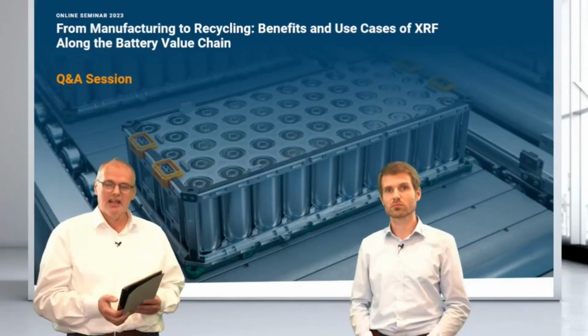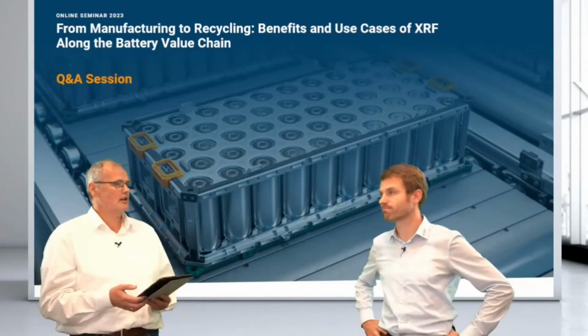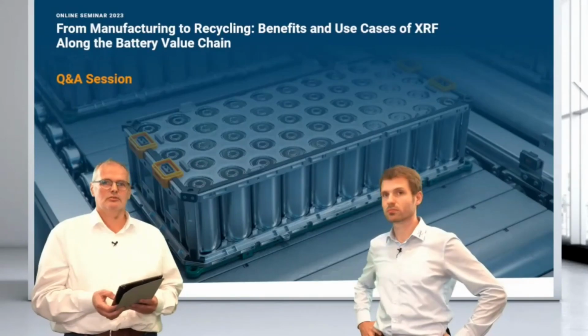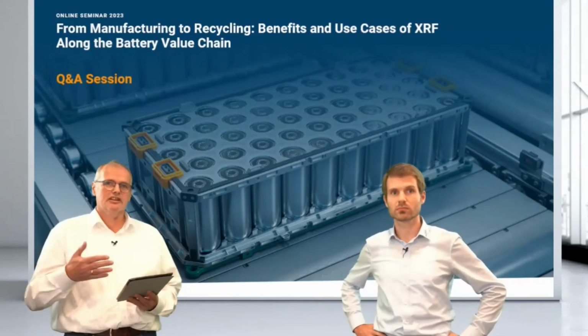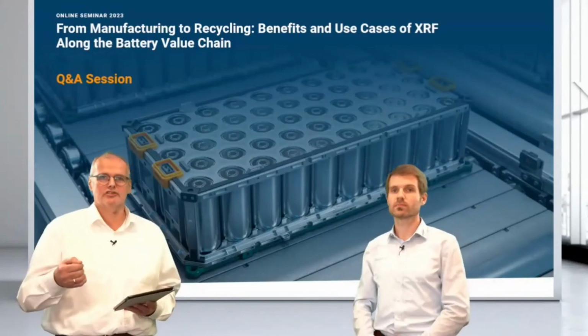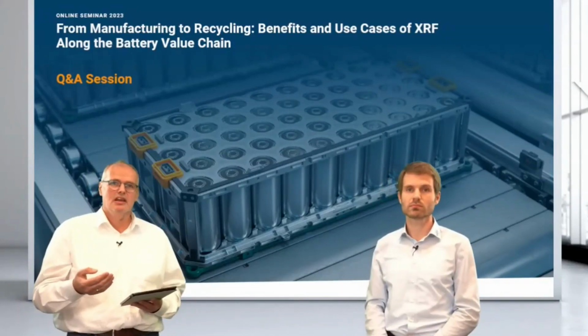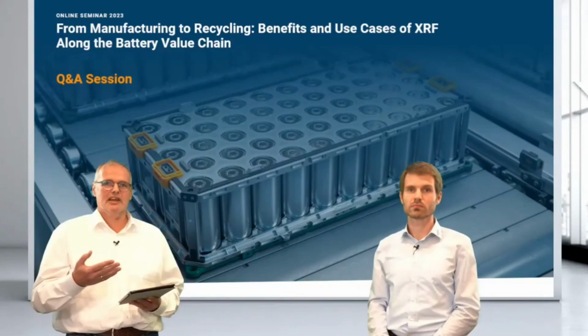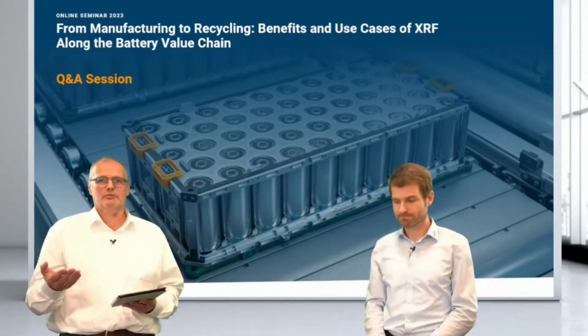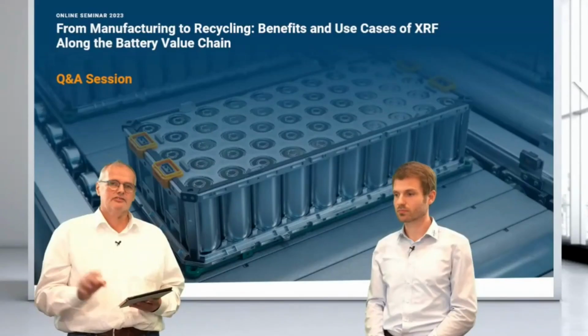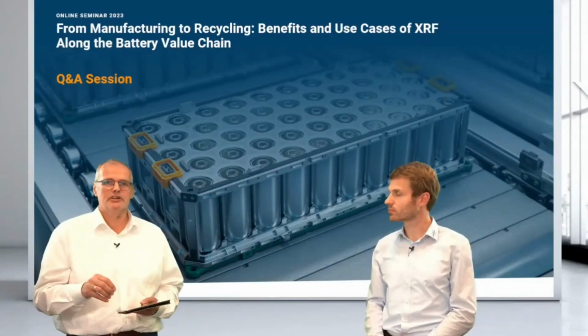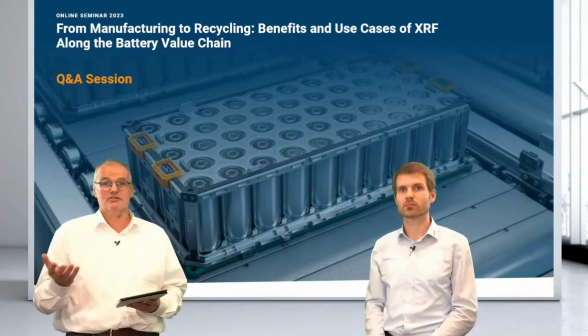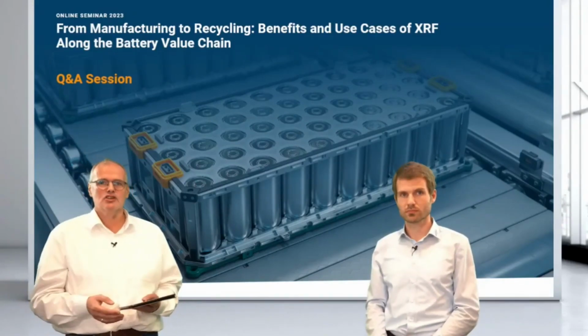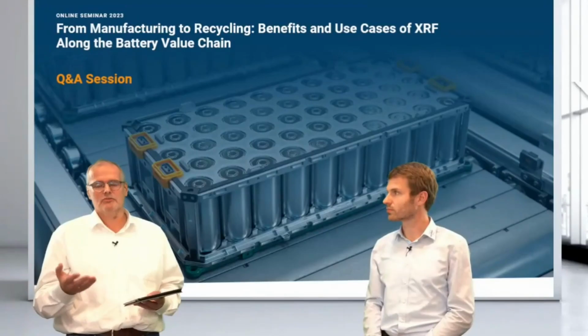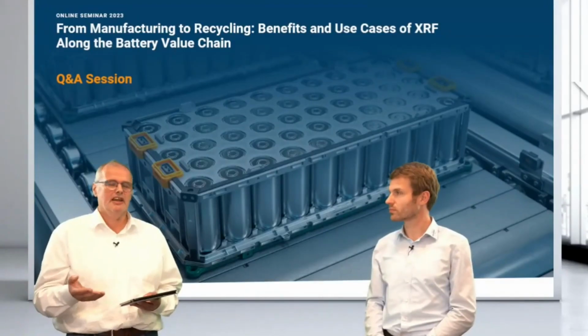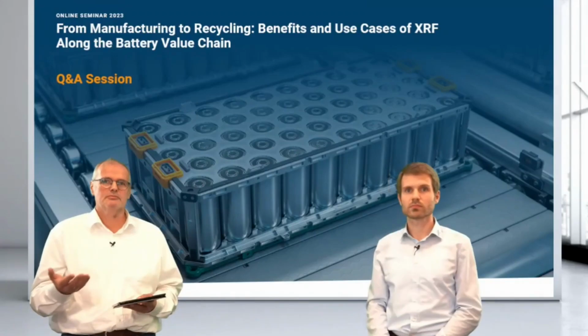Yeah. This is also the question related here. I will take this. It means, how does the software know if you analyze traces or majors? The good thing actually in XRF is that you have a huge linear range. You don't need to dilute samples. So the software or the instrument can handle ppm to 100% in one go. The interesting thing is that we have stored in a line library the optimal conditions to analyze traces, avoiding line overlaps. So whenever you are starting and preparing a method, the software will propose those measurement parameters.